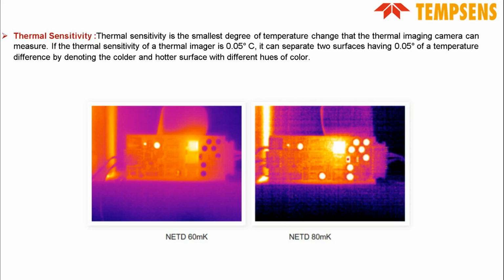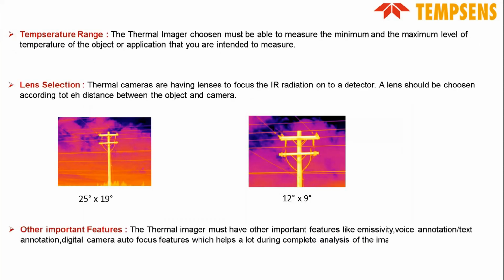Thermal sensitivity. Thermal sensitivity is basically the smallest degree of temperature change that the thermal camera can measure. For example, if the thermal sensitivity of a thermal imager is 0.05 degrees Celsius, it means that it can separate two surfaces having 0.05 degrees Celsius of temperature difference. So the lower the thermal sensitivity number, the better it is for your application, because it will give you a crystal clear image and distinguish between various surfaces.